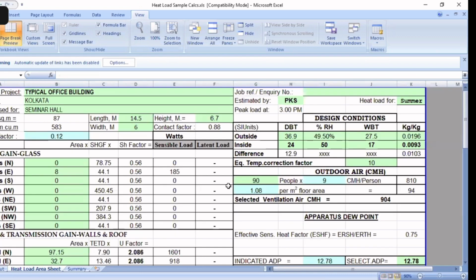Now going back to the main sheet. So this part I have done, the inside outside condition I have put, number of people I have put. Now seeing the drawing, I have seen the drawing of the seminar hall. There is a glass window on the east side. So this was the area, multiplied by solar heat gain factor, by shading factor. So this was my sensible load. Then south, there was no area, no glass. Only east side there was glass.